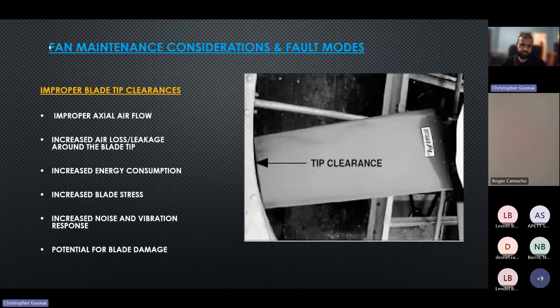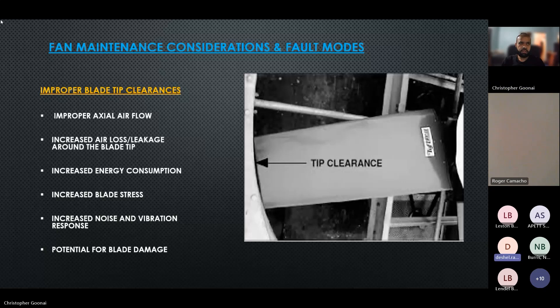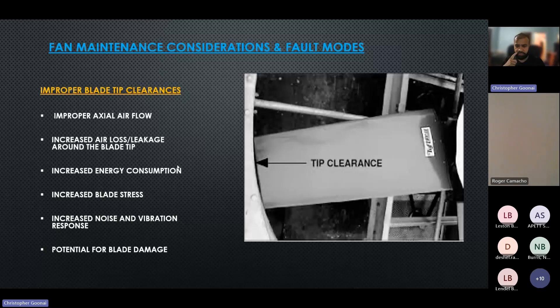Consequences of improper blade tip clearance include: improper axial flow, increased air loss and air leakage around the tip, increased energy consumption, increased blade stress, and noise and vibration — excessive clearance tends to create a lot of turbulence at the blade tip. There is also potential for blade damage, which may apply if the clearance is too tight; for example, the orbital motion induced by an unbalance could cause the blade tip to contact the shroud.